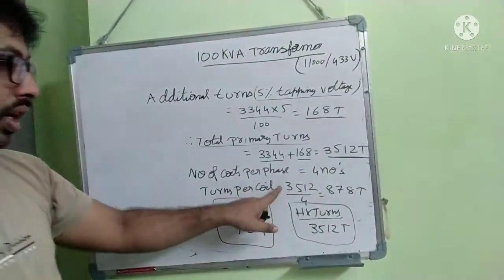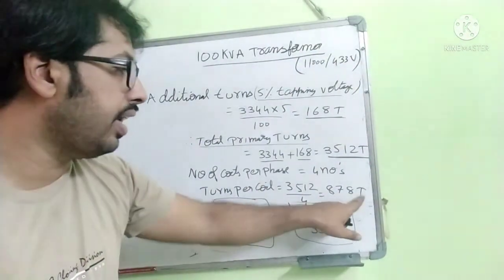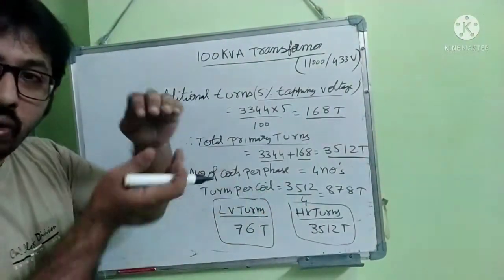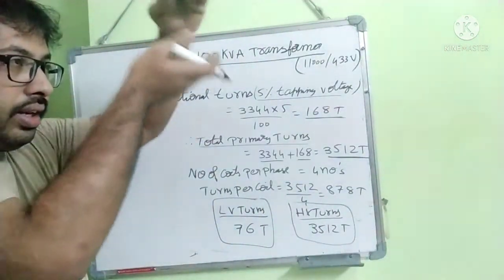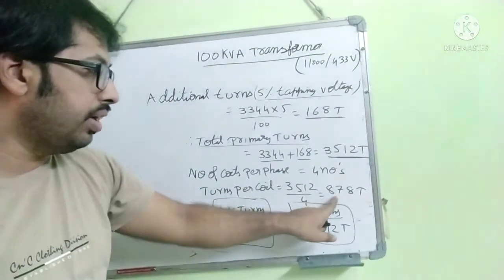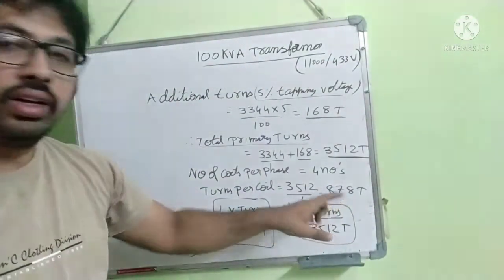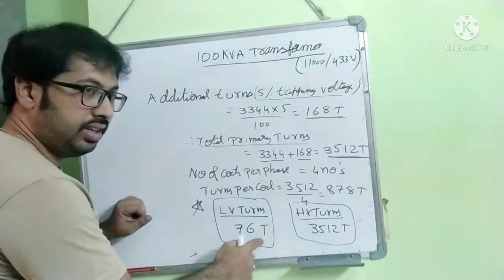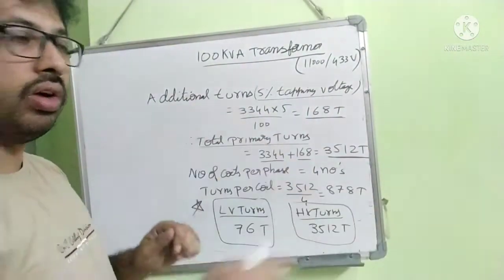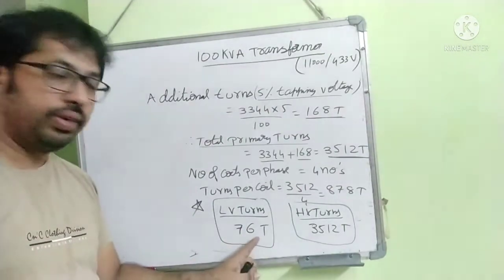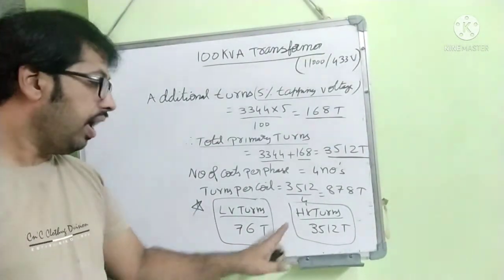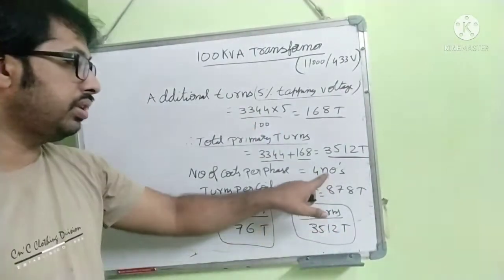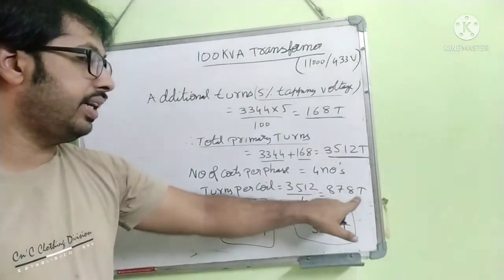So per phase, how many coils we have to place for HV winding? I think it is 4 numbers. So divide with 4. So 3512 per 4, 878 turns per coil. Like this we will keep 1 coil, 2 coil, 3 coil, 4 coils. Each coil has 878 turns. So totally today in design, we derived LV number of turns, 76 turns. We will tell the winding person to do the winding of 76 turns. And HV turns, 3512 turns. Per coil is 878 turns.